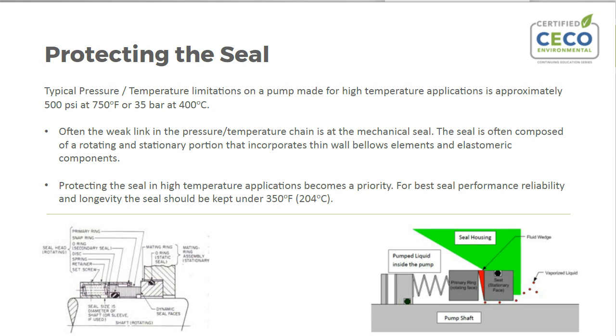The seal is, of course, composed of a rotating and a stationary portion. It incorporates thin wall bellows, oftentimes elastomeric seals, O-rings, gaskets, things of that nature. Protecting the seal in high temperature applications becomes a priority. So oftentimes the pump is built around the seal in order to protect it from the high temperature, high pressure atmosphere.